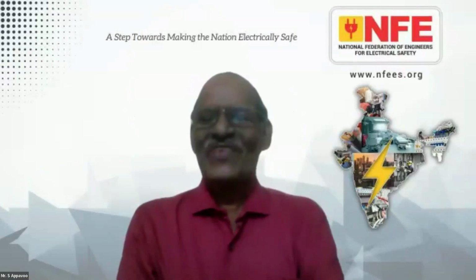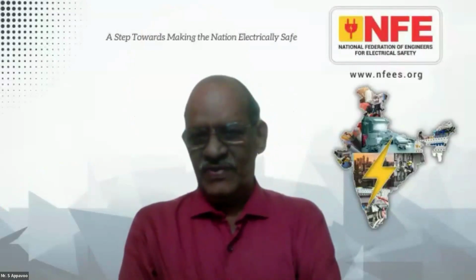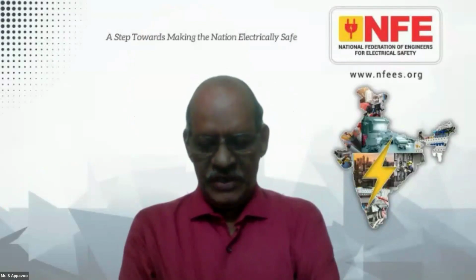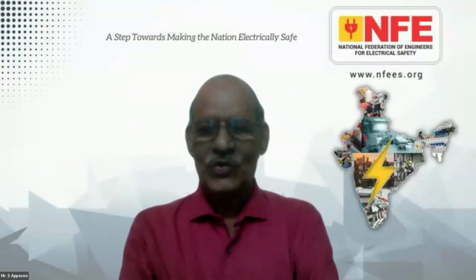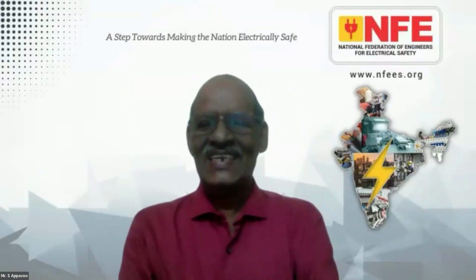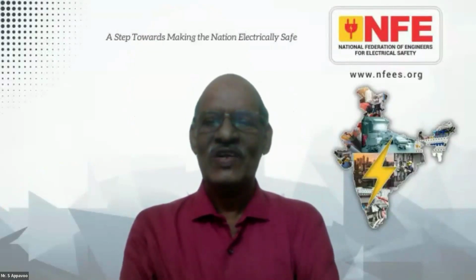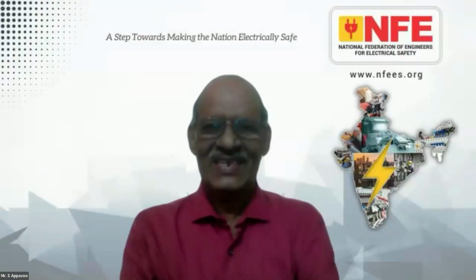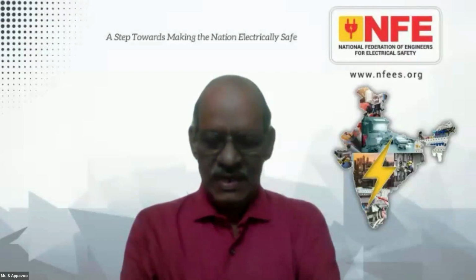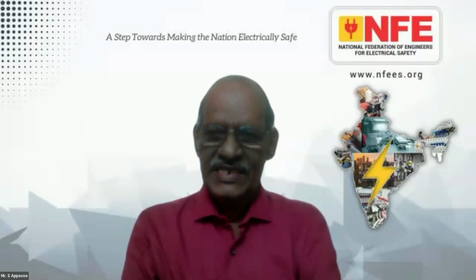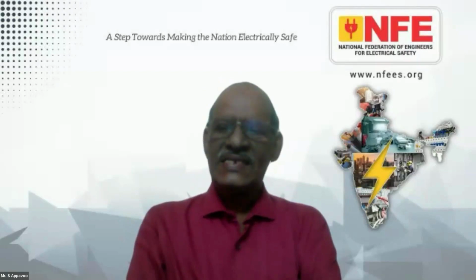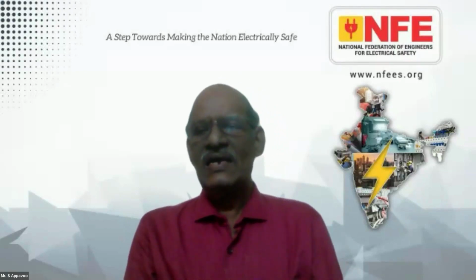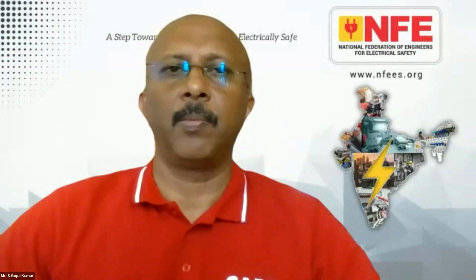It's a typical question. First of all, when we go for discharge, we have to ensure there is no voltage. If there is a voltage, if you provide any size of cable, you can't provide a 240 square SLP cable from the line conductor to the earth. The size of the discharge cable depends upon the availability of supply. For 220, I don't think a 220 kV supply will be discharged through the earth rod.